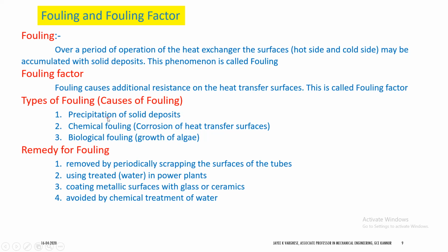Now another reason is chemical fouling. In essence, the fluid or the contaminants in the fluid will be chemically reacting with the solid surfaces through which they are flowing, and there will be corrosion taking place and the surfaces will become corroded. Such deposits are called corrosion fouling, or we call it chemical fouling. The better word is chemical fouling.